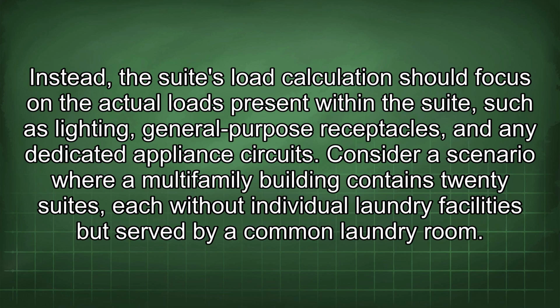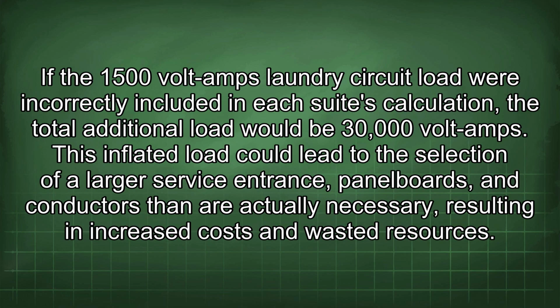Consider a scenario where a multifamily building contains 20 suites, each without individual laundry facilities but served by a common laundry room. If the 1500-volt amps laundry circuit load were incorrectly included in each suite's calculation, the total additional load would be 30,000 volt amps. This inflated load could lead to the selection of a larger service entrance, panel boards, and conductors than are actually necessary, resulting in increased costs and wasted resources.